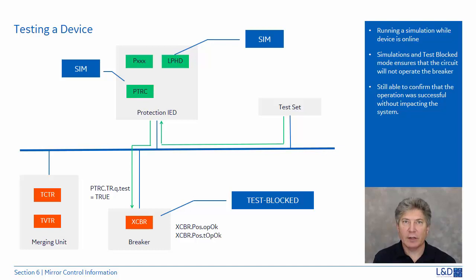However, no output will be generated since the logical node mode is set to test blocked. The output can be verified through data attribute XCBR.pos.opOk and the timing can be measured through the data attribute XCBR.pos.topok.